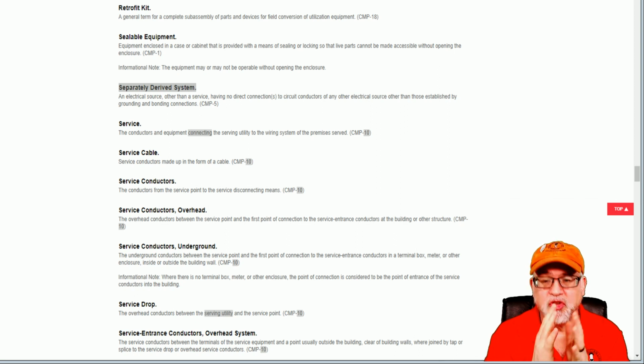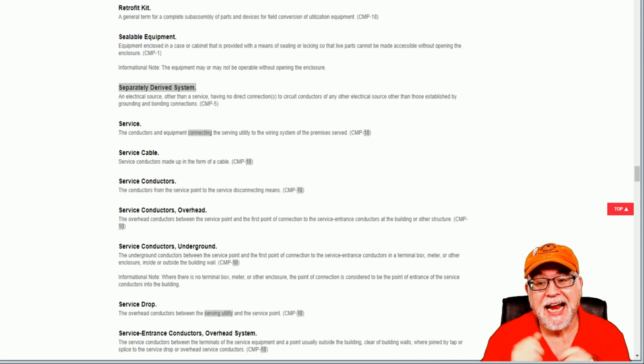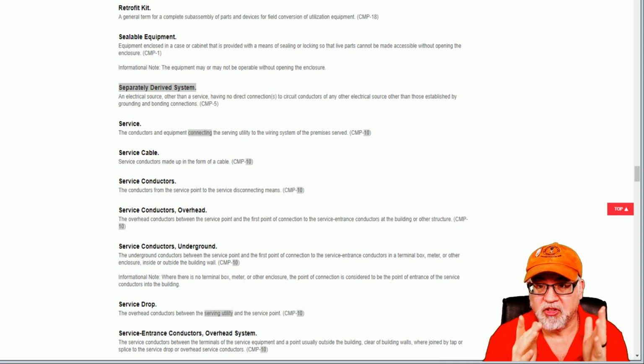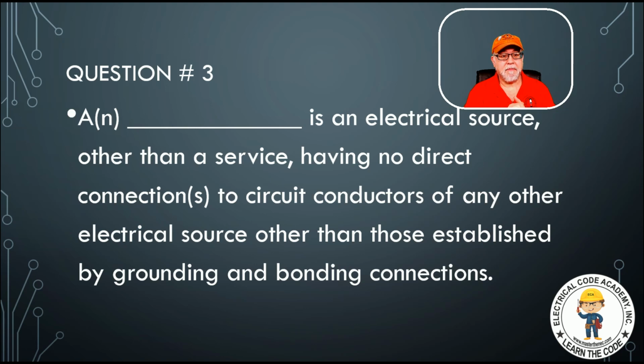But the best way to remember is that there's no direct connection between, on a transformer, primary to secondary. On a generator, there's no direct connection between the feeders that are coming in from the generator and the utility lines that are coming into the transfer switch. They aren't intimate. Again, grounding and bonding, tying everything together, is going to be intimate, but the actual circuits are not. Okay? So, takes us back to our presentation a little bit. Hopefully you got that. So, a separately derived system is an electrical source other than a service. Remember, generators are not a service, okay? They are an electrical source, and those are feeders that are coming in from it, okay?